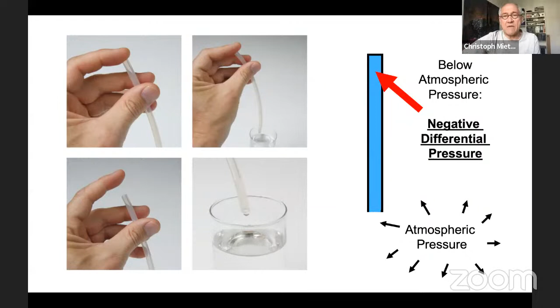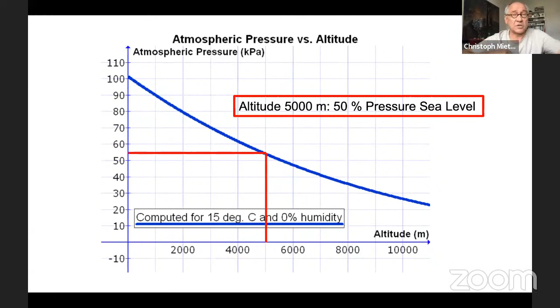If I mention negative pressure now, I have to address that the absolute pressure is not stable, and it's completely different to the differential pressure. The absolute pressure is the atmospheric pressure, which depends on the altitude. If we climb mountains at a height of 5,000 meters, we have about 50% of the absolute sea level pressure, which means maybe 500 millibars, and at sea level we would have 1,000 millibars. Our ICP is adapted to the change, and the differential pressure is still, let's say, 10 centimeters of water.